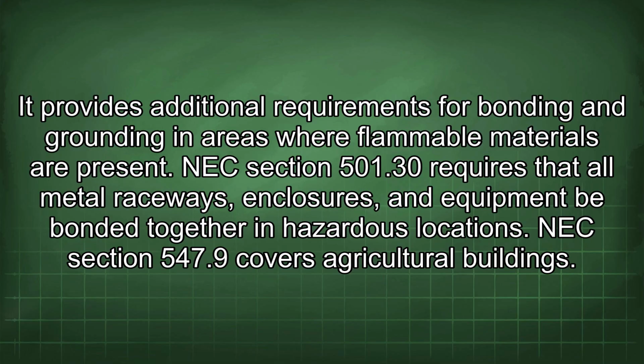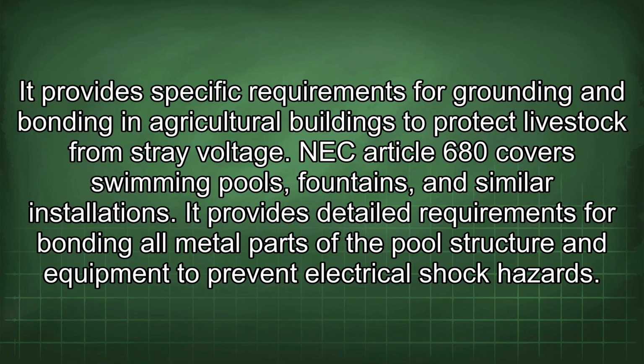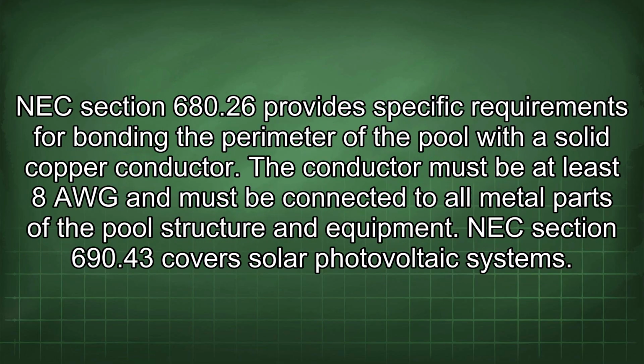NEC Section 547.9 covers agricultural buildings. It provides specific requirements for grounding and bonding in agricultural buildings to protect livestock from stray voltage. NEC Article 680 covers swimming pools, fountains, and similar installations. It provides detailed requirements for bonding all metal parts of the pool structure and equipment to prevent electrical shock hazards. NEC Section 680.26 provides specific requirements for bonding the perimeter of the pool with a solid copper conductor. The conductor must be at least 8 AWG and must be connected to all metal parts of the pool structure and equipment.